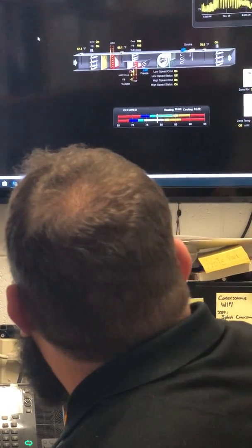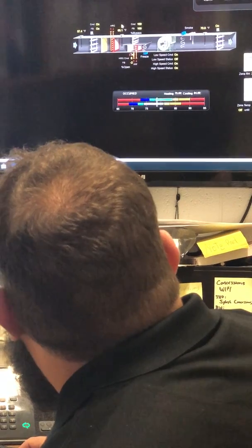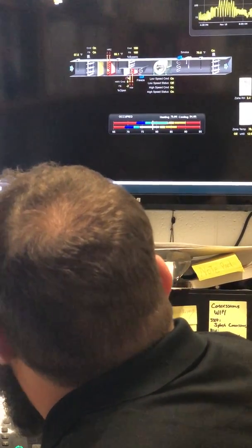Outside air, so supply air, we've got 57.3 degrees. That was the actual temperature probe that you were recording earlier. It goes through the air dampers, the pre-filters, which you saw. And then you have your heat coil. Right now, heat recovery. If you notice, we go from 57.6 to 66.1. We're getting that increase across there. That's because of that heat recovery coil. And then through here, we have our actual heat coil.